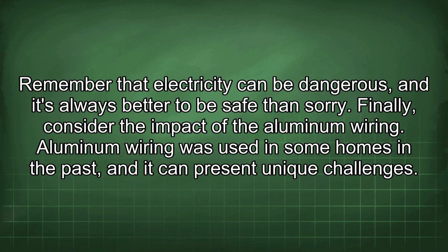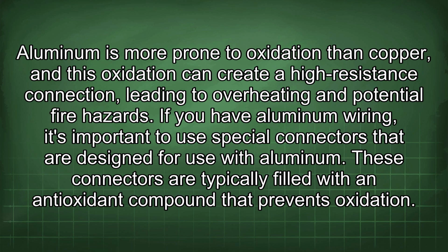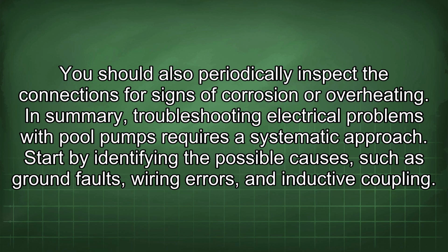Finally, consider the impact of the aluminum wiring. Aluminum wiring was used in some homes in the past, and it can present unique challenges. Aluminum is more prone to oxidation than copper, and this oxidation can create a high resistance connection, leading to overheating and potential fire hazards. If you have aluminum wiring, it's important to use special connectors that are designed for use with aluminum. These connectors are typically filled with an antioxidant compound that prevents oxidation. You should also periodically inspect the connections for signs of corrosion or overheating.